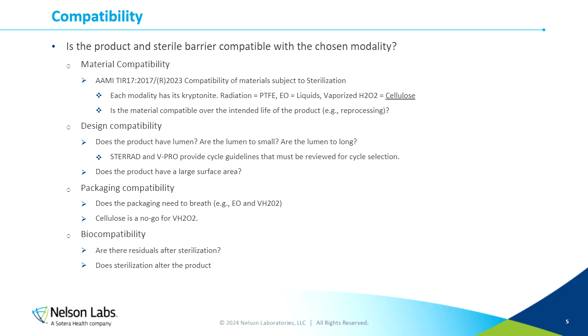For example, if we only have a small area exposed that's breathable and we're stacking those against each other, such as a Tyvek poly pouch, where the Tyvek side is covered by the poly side, we're not going to have as good of exposure as we may potentially like. Another thing, again, make sure and consider that cellulose, it's a no-go. So cellulose packaging is not going to be an option for vaporized hydrogen peroxide.